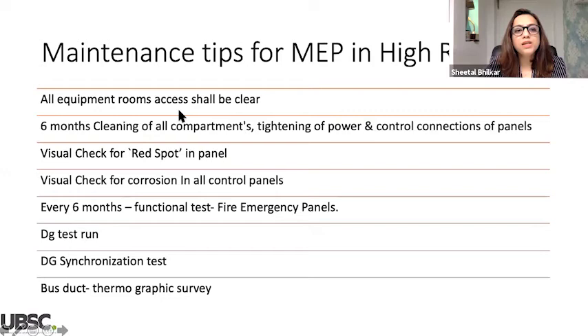So first of all, equipment room access should be clear. Many times after handing over, people use those passages for different things, and then something is lying there, and when maintenance comes, that access is not clear, so that should be taken care of. Then every 6 months, cleaning of all compartments and tightening of power and control connections for panels should be taken care of. Visual checks for red spots in panels should be done. Then a visual check for corrosion in control panels every 6 months. A functional test for fire emergency panels is very important, because these are all life safety systems.